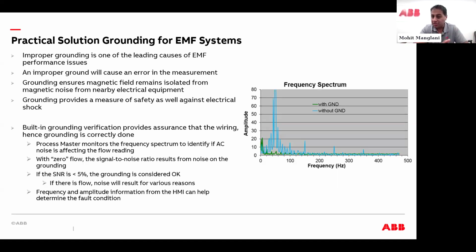So we did an analysis to validate this: if I ground the device or cross-bond the device, I have a much more stable signal and much better accuracy. If I don't have a ground or a cross-bond, you can see noise picking up depending on situations that are happening in the field.